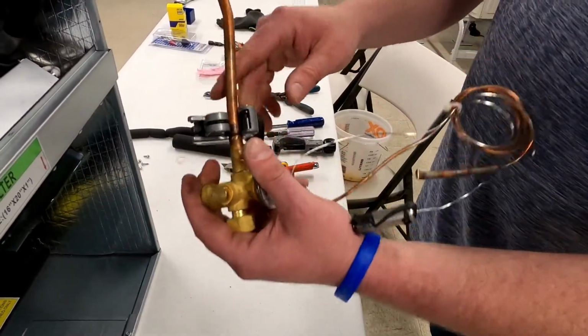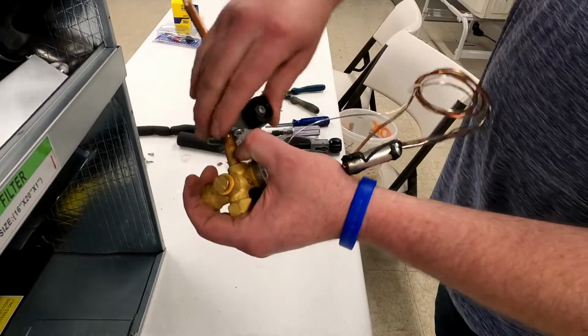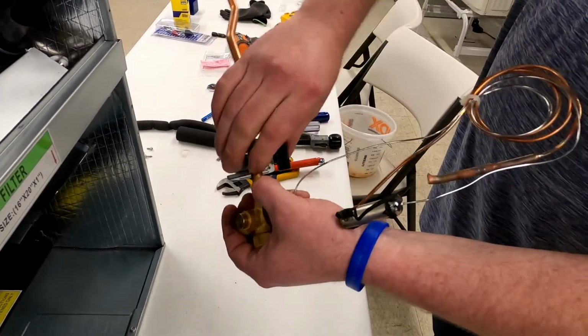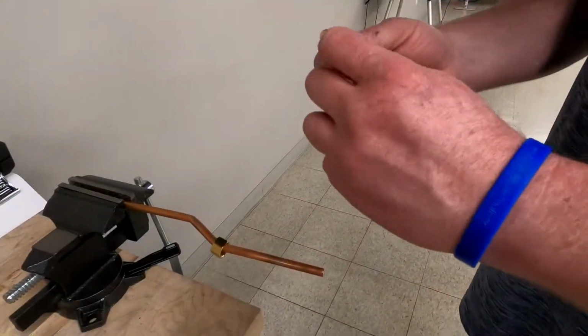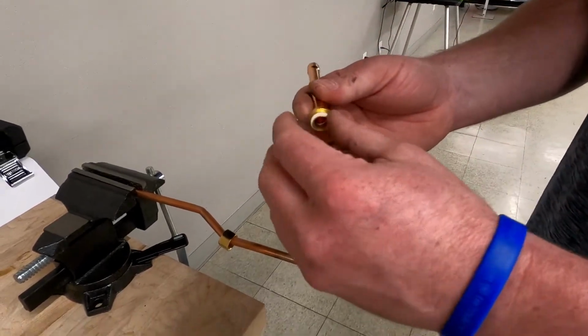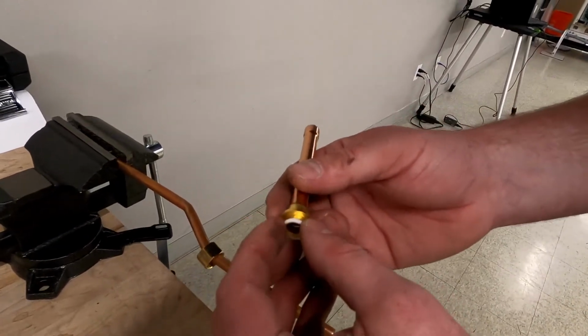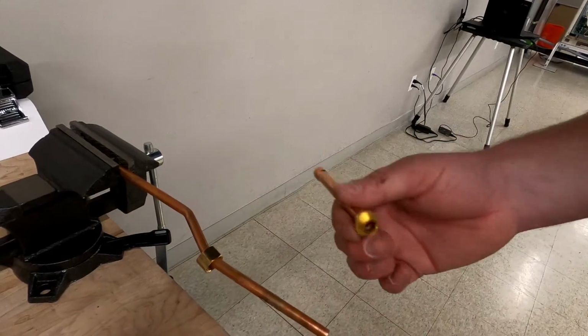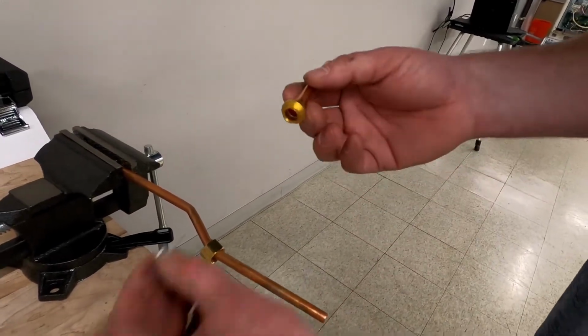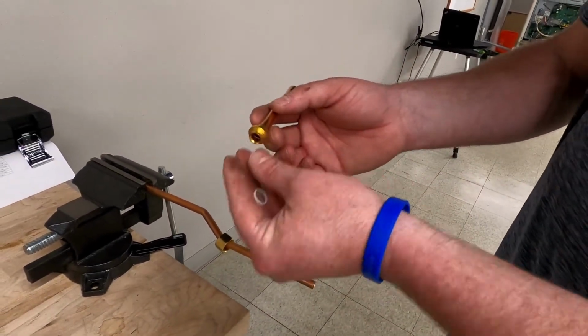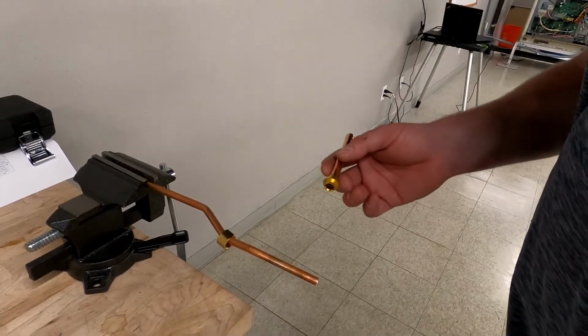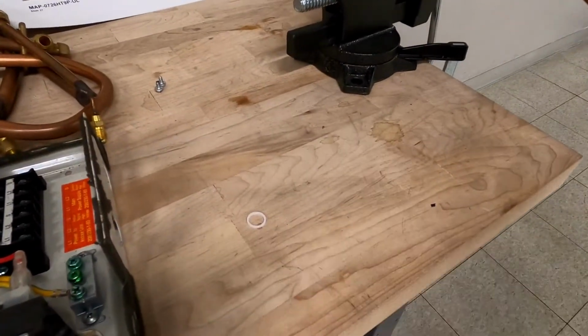So now we mark where we want to cut the pipe at. Now we're going to cut it off the TXV. My suggestion is that you braze the adapter fitting to the piece of pipe that you cut off outside of the unit. It'll give you much more room. Now when you're doing that, you want to be sure to remove the Teflon seal on the adapter fitting before you braze it.